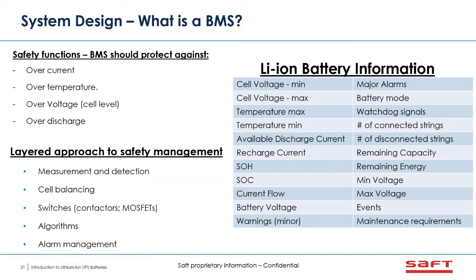And then what is a BMS? BMS is a battery management system that's required for lithium-ion batteries. But what I'm showing here in the top left is what any BMS should protect against, the main safety functions. So your BMS should protect against overcurrent, so making sure that the battery strings are not overloaded.